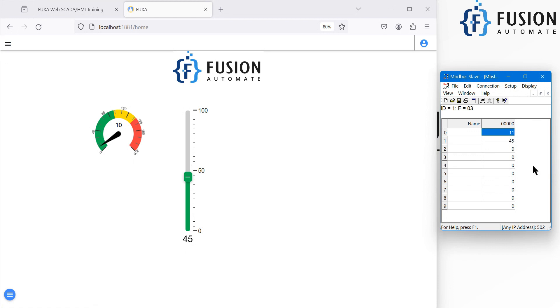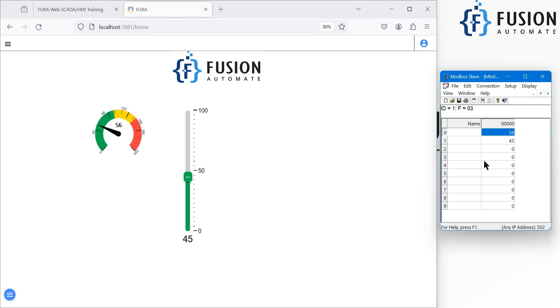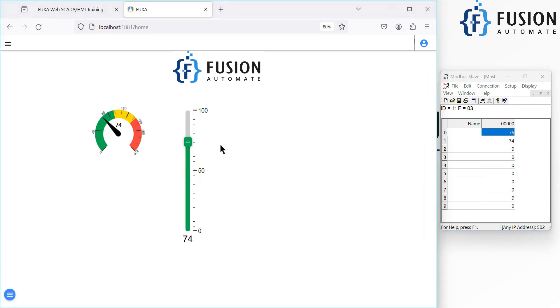This is how you can read data from your Modbus TCP device. Your Modbus TCP device can be anywhere on your network — that doesn't matter. You can connect FUXA SCADA to it, read values from it, and also write values to it. We've covered holding registers here, but you can also experiment with input registers, input status, and coil status. You can update coil status or read input registers — useful if you have an inverter or Modbus gateway in your plant.